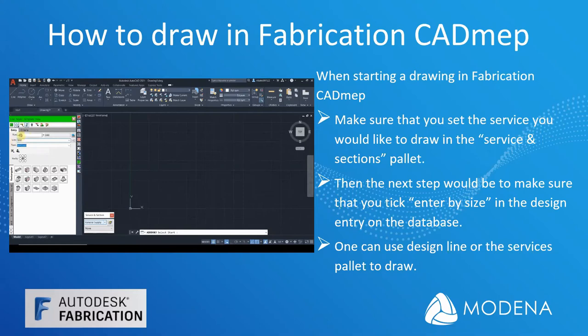And then from there, we'll give it a size. So okay, let's give it 700 millimeters. And then we'll give it a height of about 500. And then once that's done, we can click on design line, and then there we go. We basically draw like this. As you can see, I've started drawing. Once you draw, it basically populates with hangers. So as you can see, it's populating as I draw. As I move up, down, in any direction, it basically populates and gives me my hangers, and also populates the correct duct sizes as per the database.